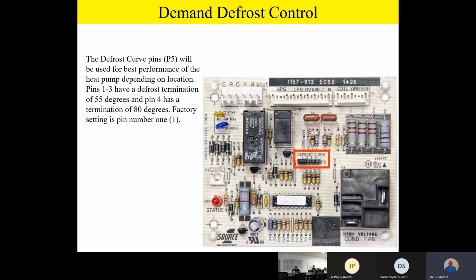Or maybe you have freezing rain in Tennessee, and you want to have a higher defrost termination point. The point is that I recommend leave it where it is, unless you have a real good reason to change that to 80-degree termination. Because if you put it on the 80-degree, pin number 4, what's going to happen most of the time is you're going to be going out on not time temperature, excuse me, you're going to be going out on a time backup of 14 minutes. And so if you move it over to 80 degrees, it's going to sit here and cook and cook and cook and defrost and all that stuff until you hit the time backup.